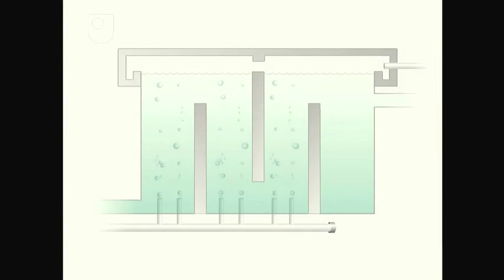To ensure adequate treatment, the gas is released at several points. And as the water is forced through the tank, it has to negotiate baffles that ensure it remains in contact with the ozone for as long as possible. The dead algae are held in suspension and are carried forward to the next stage.